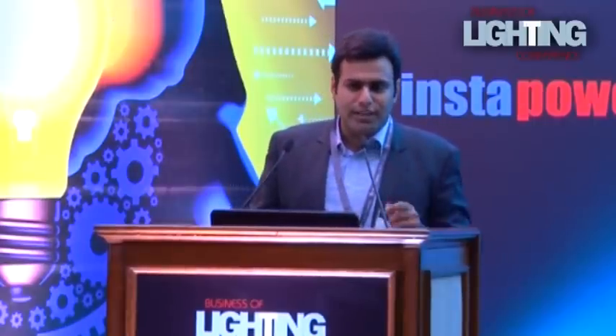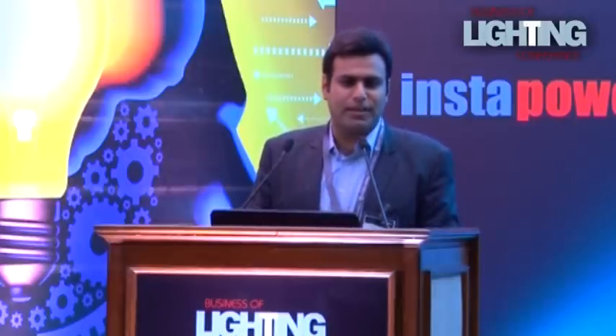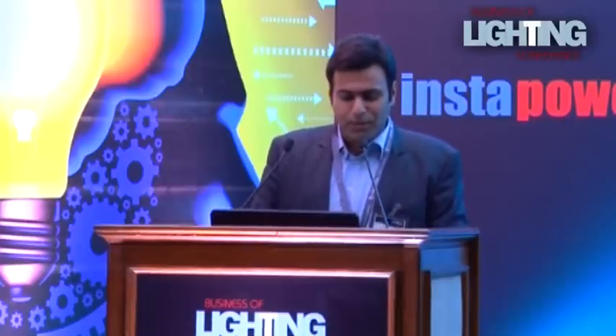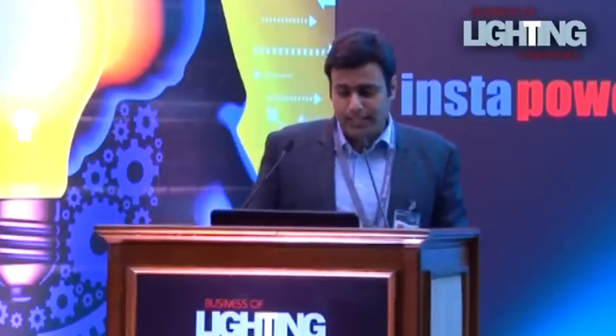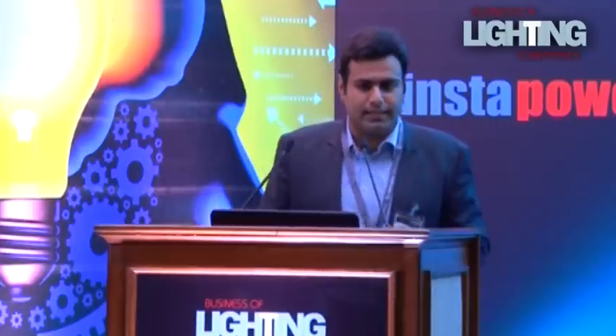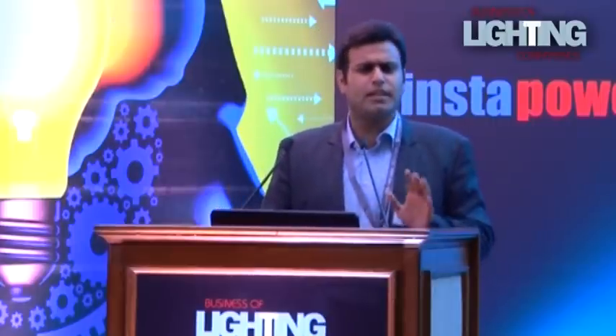So if I just quickly take you back to where I started: 45 fixtures and an LPD of 24. Now I've reduced it to 24 fixtures with an LPD of just 5.86 watts per square feet, which is required in the industry. Integrating LEDs and replacing the T8s, I get way better uniformity within my workstation area, and I get 500 lux on my workstation areas, and not on my ambient lighting areas, not on my corridors, which is really not required.